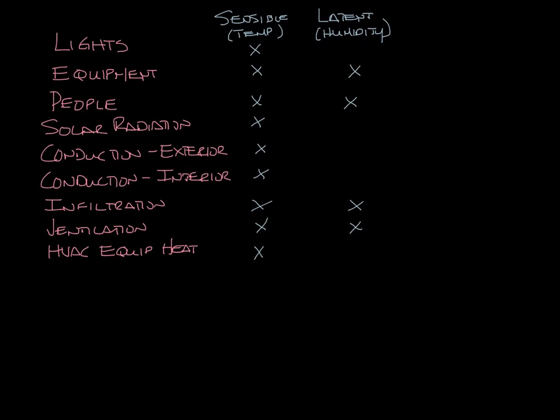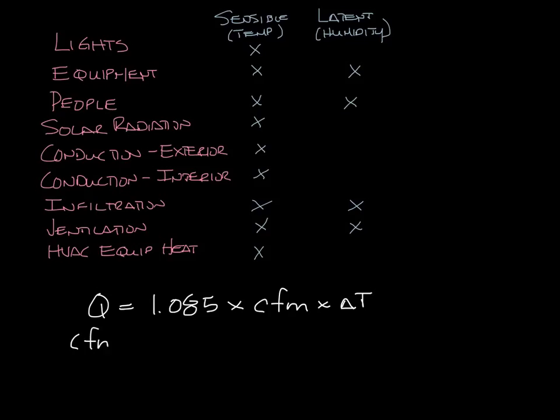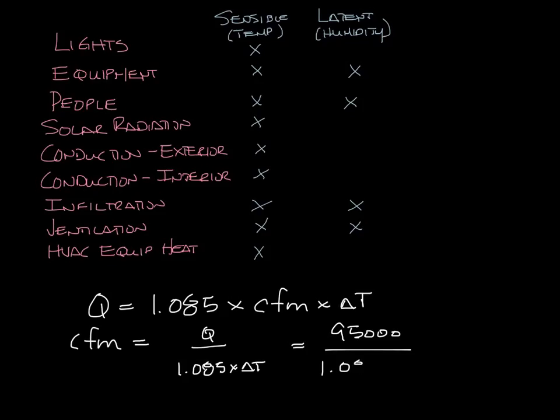In the last podcast, I talked about the load equation: Q equals 1.085 times CFM times delta T. So you can calculate how much airflow you need once you know the loads Q. CFM equals Q divided by 1.085 times delta T. So let's say we've got a total load in a building of 95,000 BTU. You're supplying 55-degree air and you want your space to be 75 degrees, so that's a 20-degree delta T. When you do the math, that comes out to 4,377 CFM — so you need about 4,400 CFM to handle the load of this space.